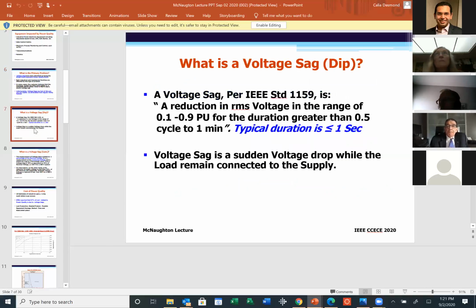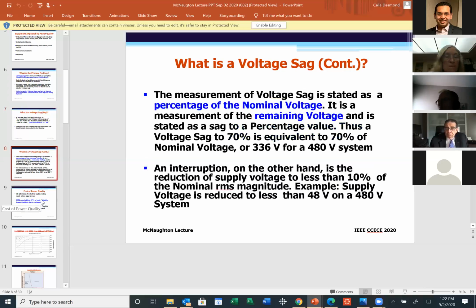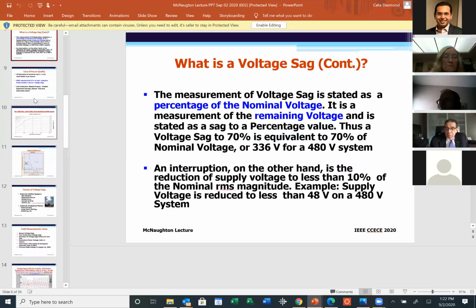What is a voltage sag? Basically, when the supply voltage at the facility drops to between 10% and 90% of its rated value, over a window of 0.5 cycle, which is about 8 milliseconds, to 1 minute. Typically, as I have indicated, the durations that are problematic are less than 1 second. That's the area we're talking about, and I can show you in other slides that most of them are in the order of 200 milliseconds. The other definition of voltage sag is a sudden voltage drop while the load remains connected to the supply. Next slide, please. There are measurements that will provide us at a plant the value of the voltage sags.